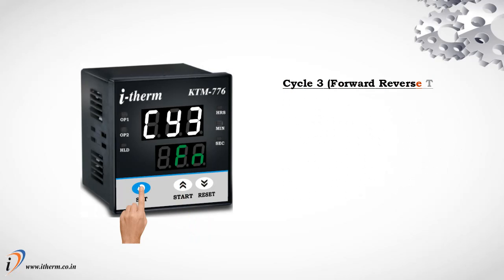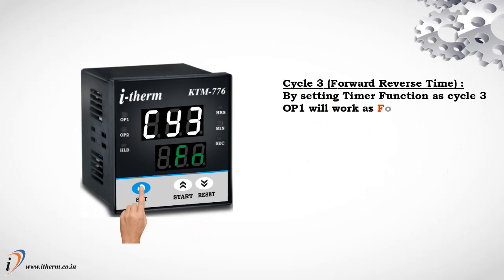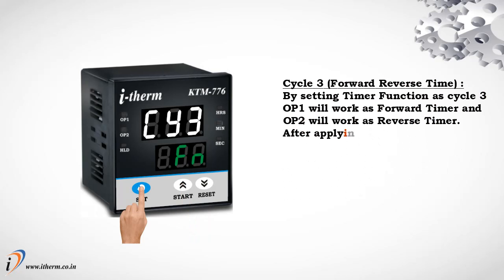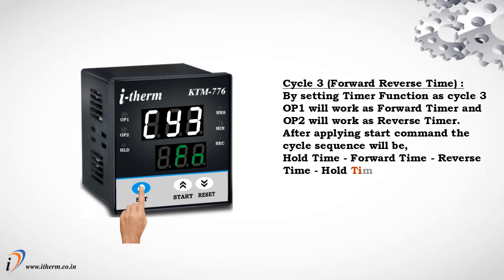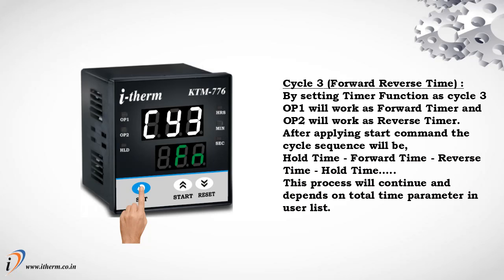Cycle 3 — forward/reverse time. By setting timer function as Cycle 3, Output 1 will work as a forward timer and Output 2 will work as a reverse timer. After applying the start command, the cycle sequence will be: hold time, forward time, reverse time, hold time. This process will continue depending on the total time parameter in the user list.